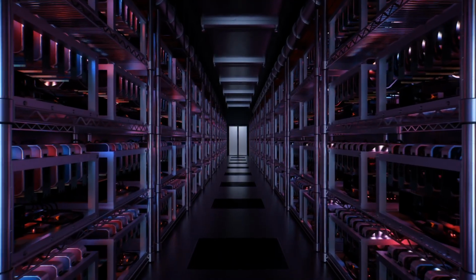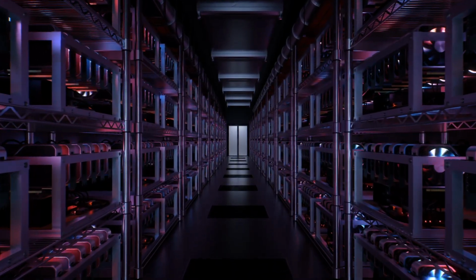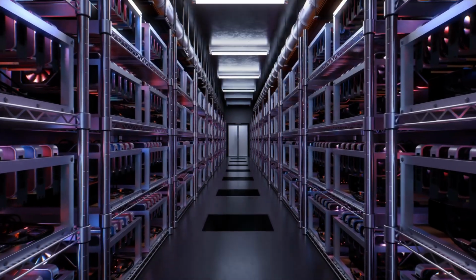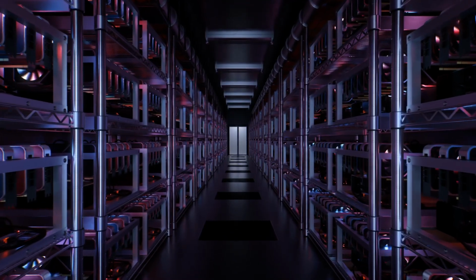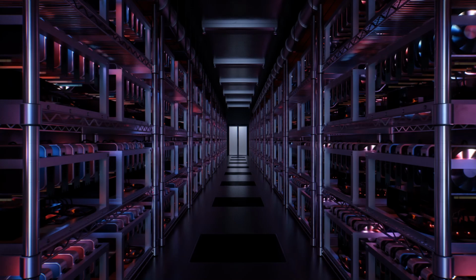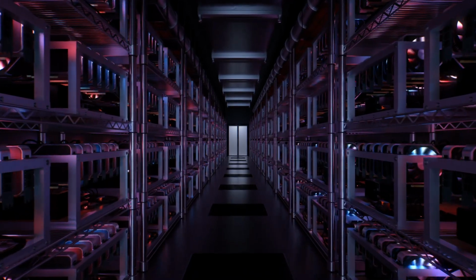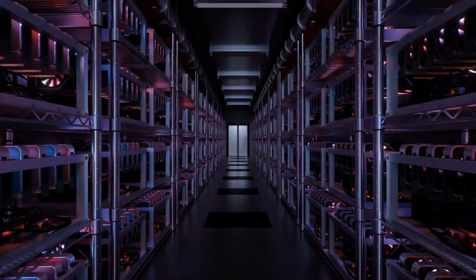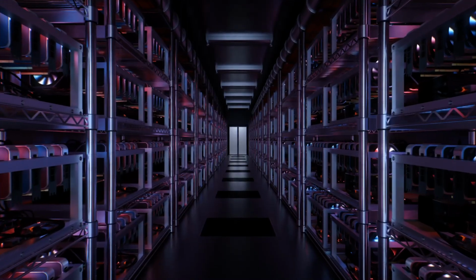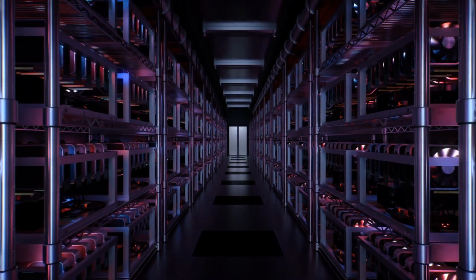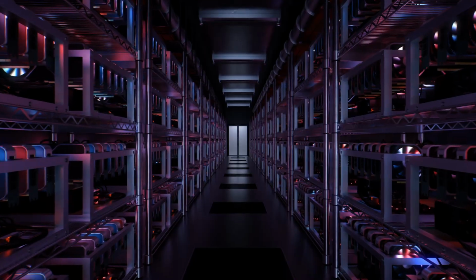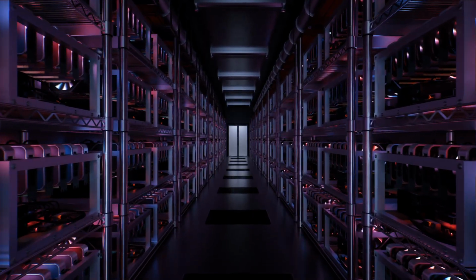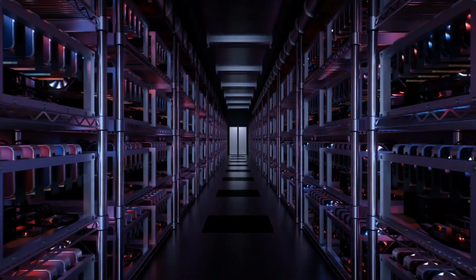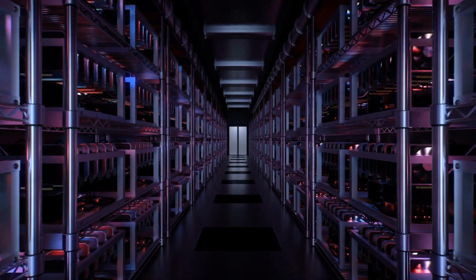Remember that the facility water, the raw street water coming into the building, can enter the heat exchanger at temperatures as low as 2 degrees Celsius. Right, which is just barely above freezing. Now, picture a large, uninsulated metal pipe carrying a massive volume of 2-degree water, routed straight into a server room where the ambient air temperature might be 35 degrees Celsius, which is about 95 degrees Fahrenheit. I see where this is going.